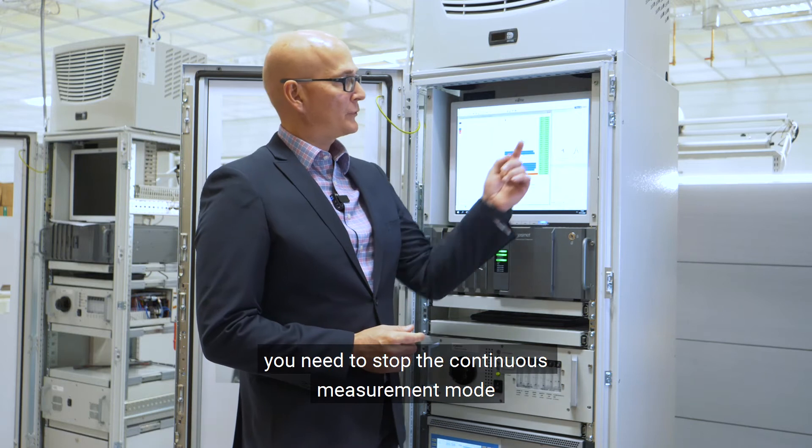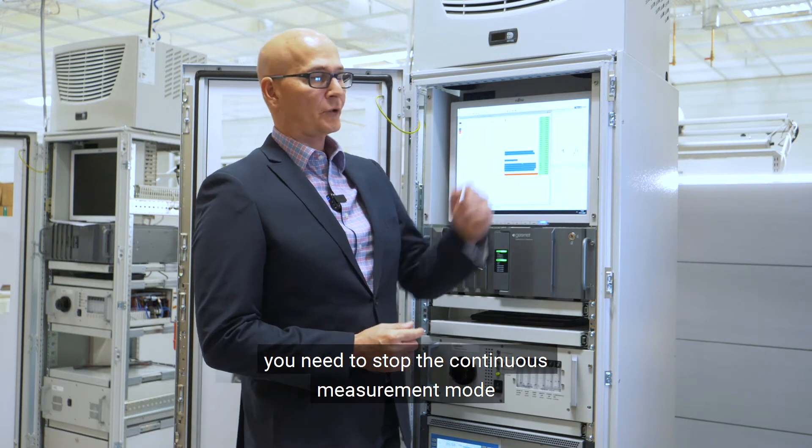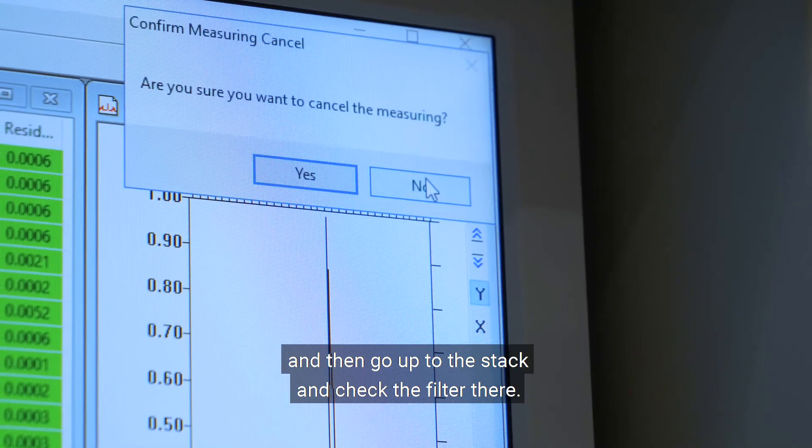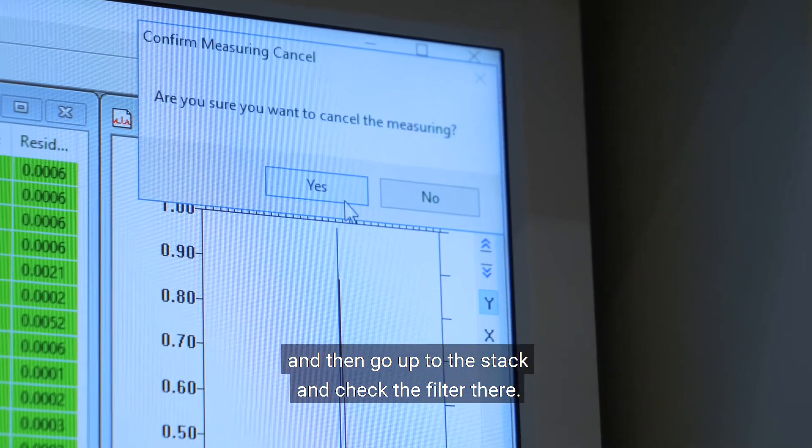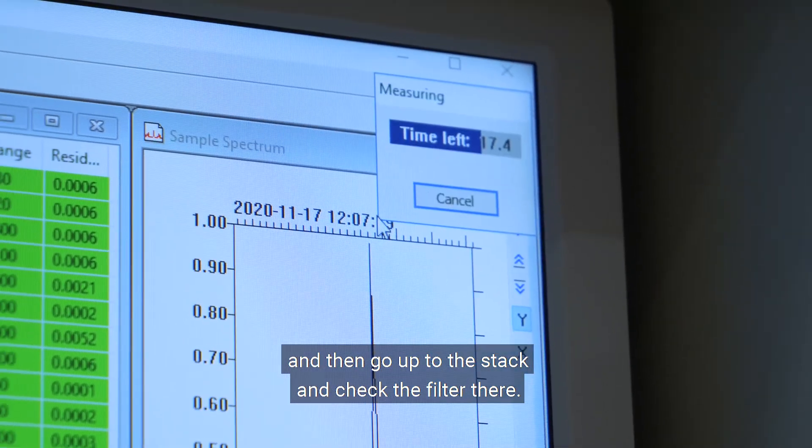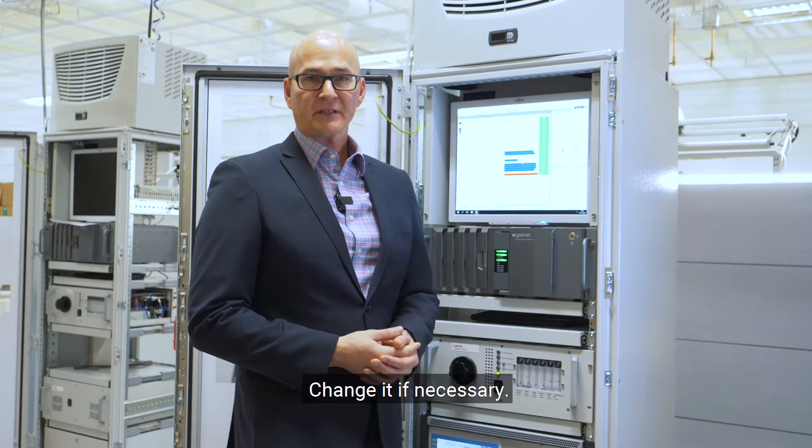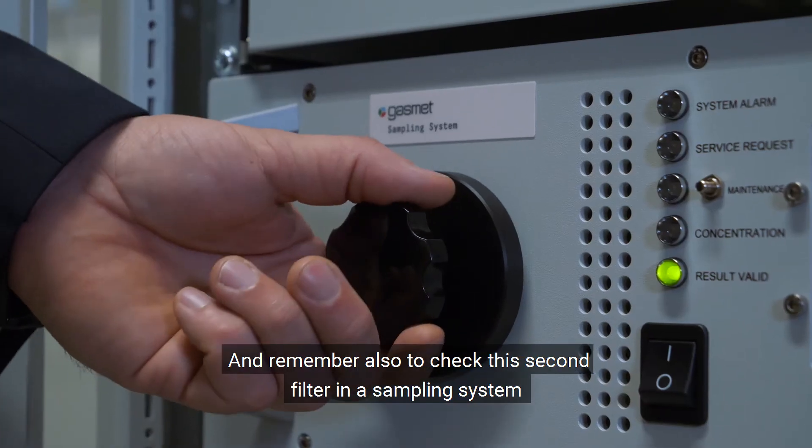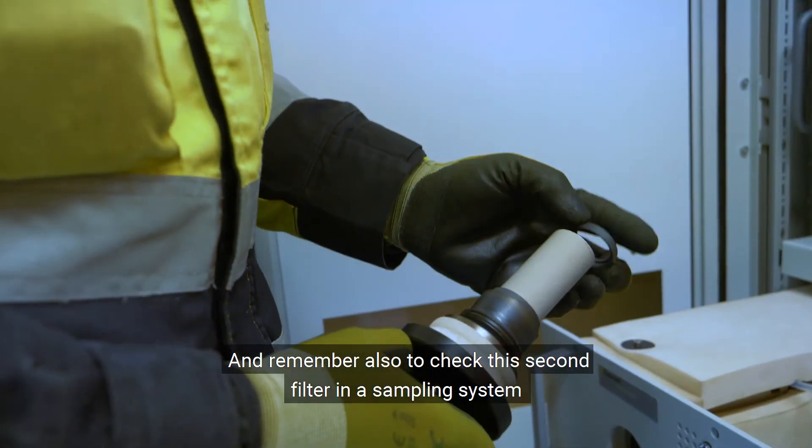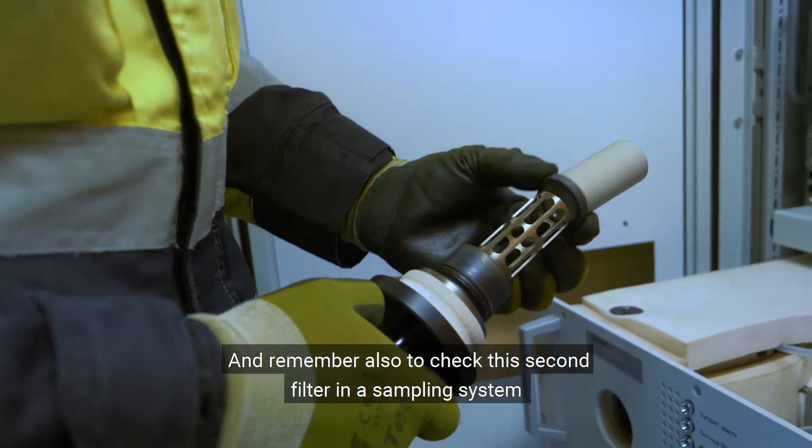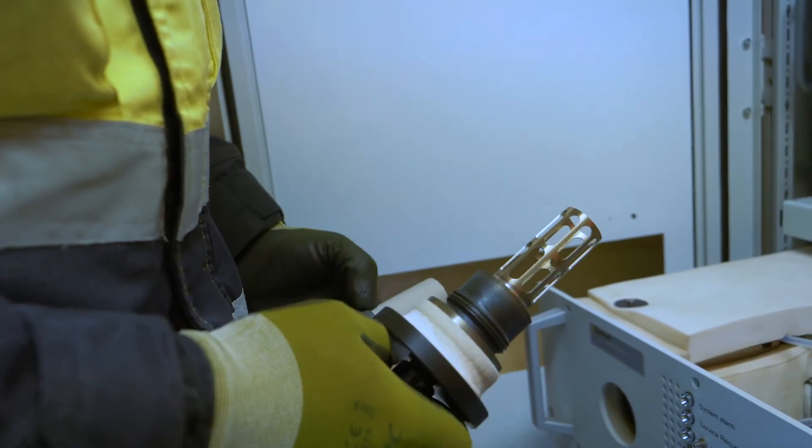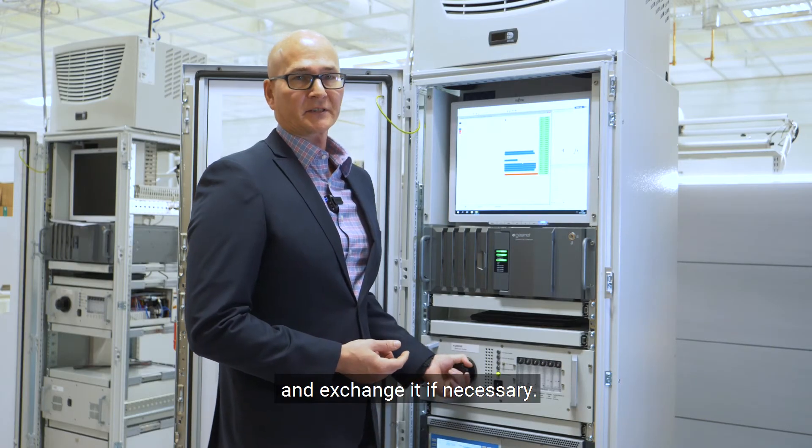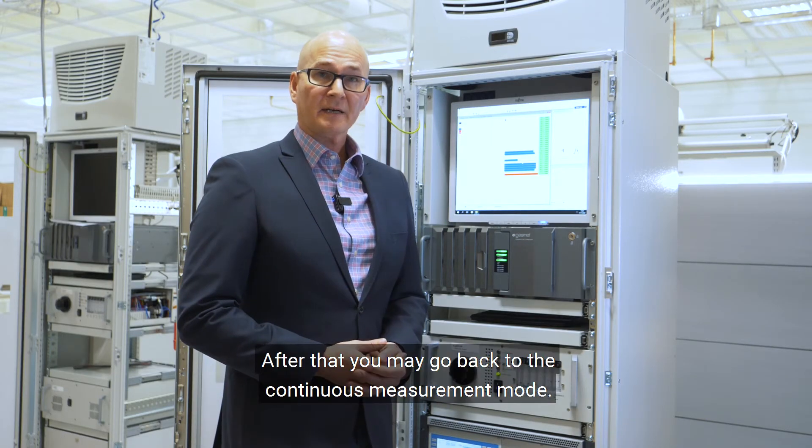You need to stop the continuous measurement mode and then go up to the stack and check the filter there. Change it if necessary. And remember also to check this second filter in the sampling system and exchange it if necessary. After that, you may go back to the continuous measurement mode.